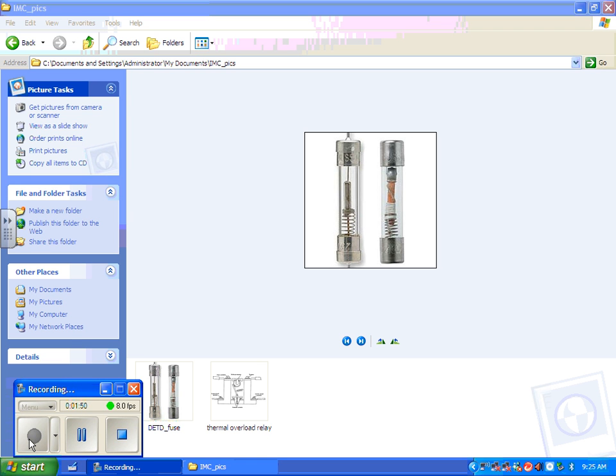So, yes, that's true. Personally, as a point of reference, as a contractor and a foreman, I would never, ever do that. All you're saving is a motor starter, and you probably need the control of the motor starter anyway, so there's not much sense in protecting the motor with just the fuses. Forewarned is forearmed. Take it for what it's worth, and there we go.